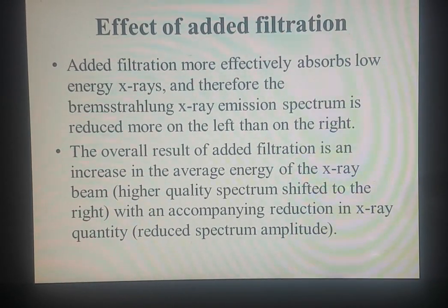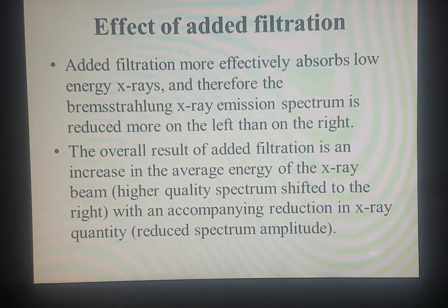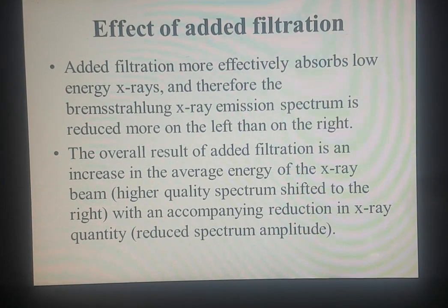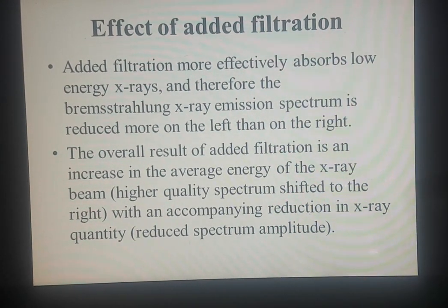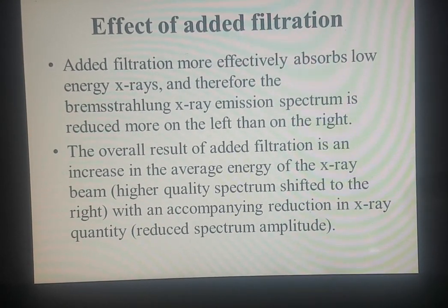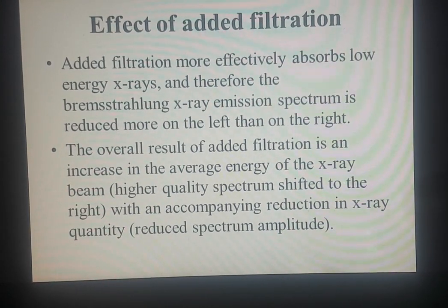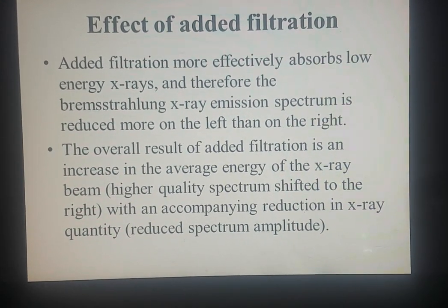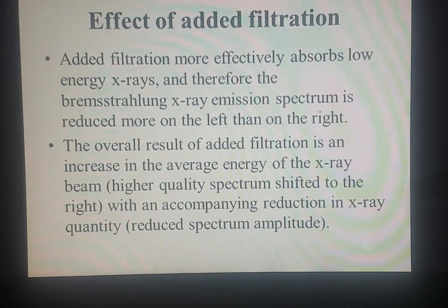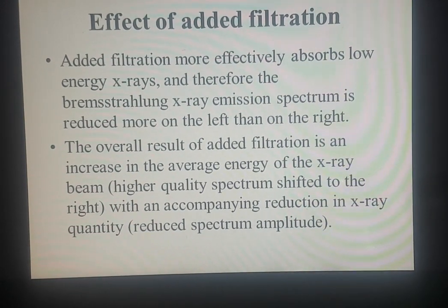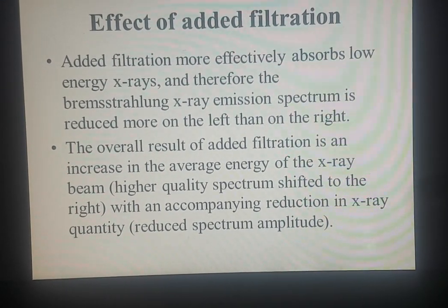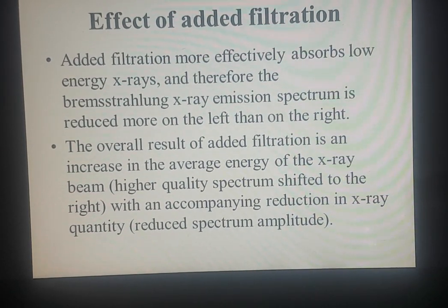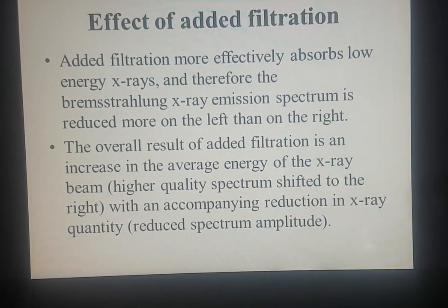The overall result of added filtration is an increase in the average energy of the X-ray beam, a higher quality spectrum shifted to the right, with an accompanying reduction in X-ray quantity, which is the reduced spectrum amplitude. So there will be reduced spectrum amplitude as there will be a reduction in X-ray quantity, and there will be the position shift towards the right.